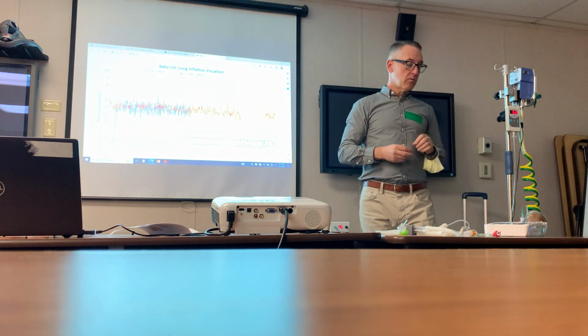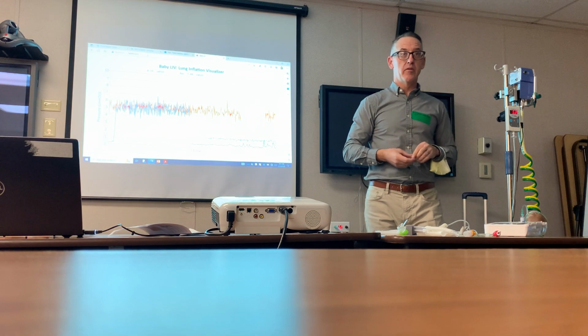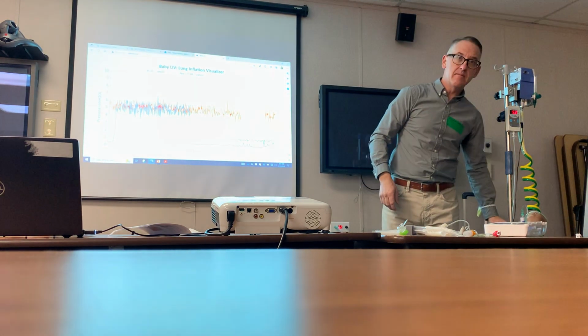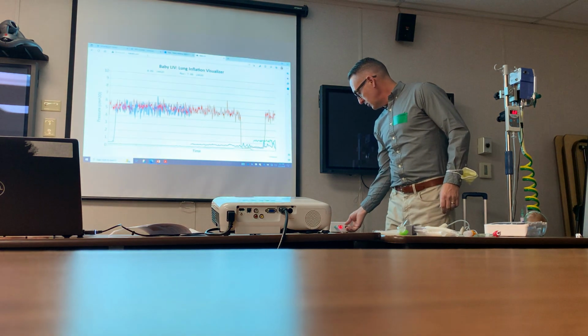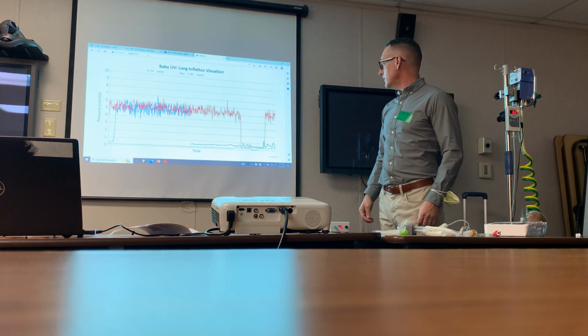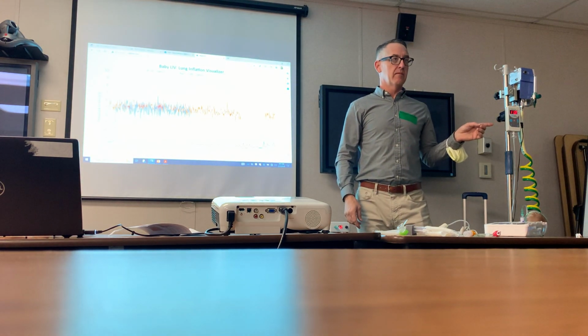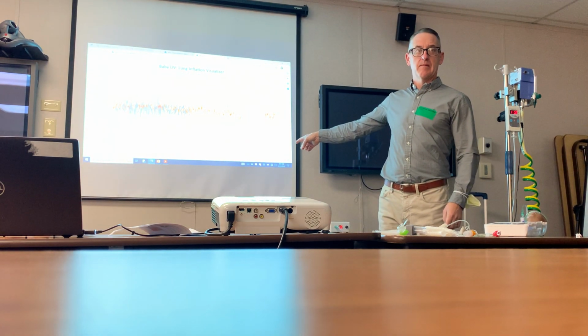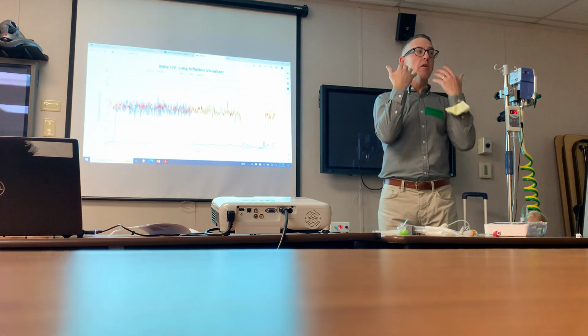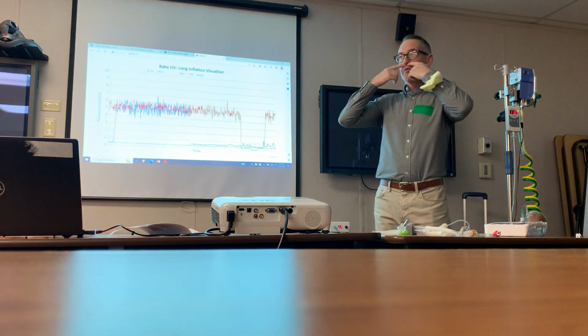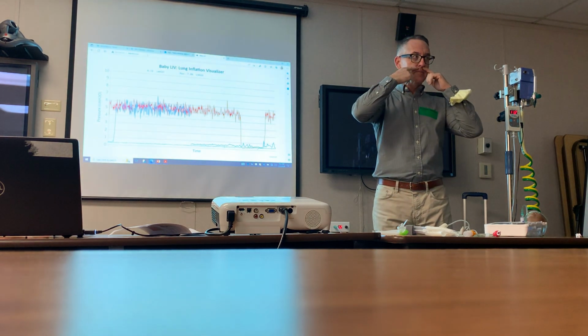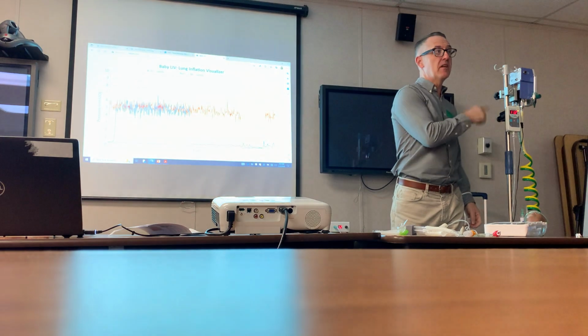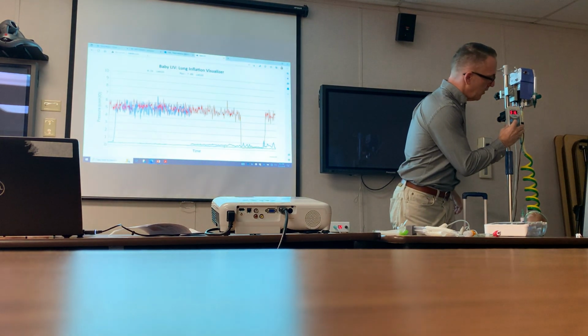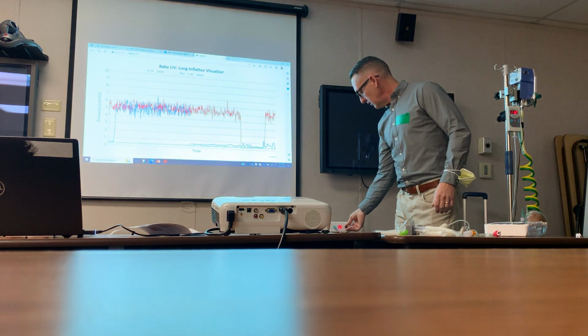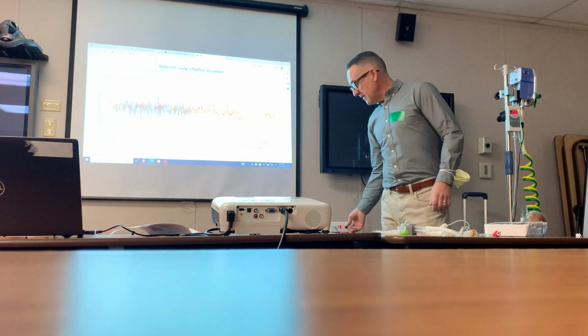So the next logical answer is we're going to titrate to effect, right? We've heard that. So let's increase the CPAP to 10. Let's increase the flow to 12. Now my manometer tells me, how much am I giving? 11. How much have I moved up the actual pressure to the baby? Because they're losing all the pressure out of their mouth and through the side of the nose with a 60 to 80% occlusion. Okay, so that's when you start getting the variable. But the information you're receiving, whether it's nasal IMV or bubble CPAP, changes dramatically. Any questions on that?